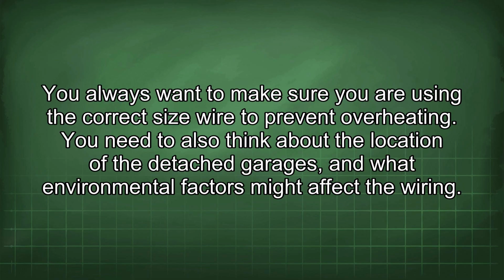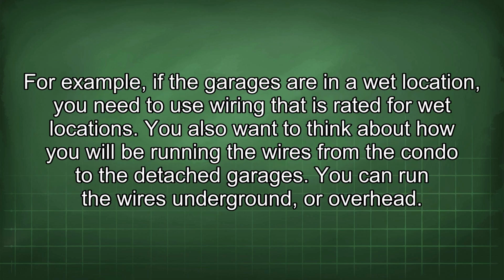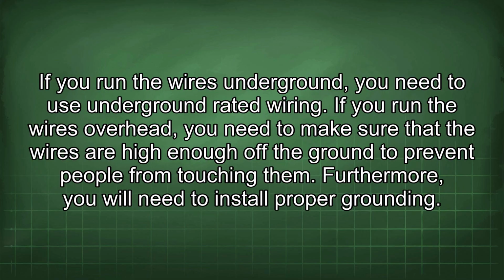You need to also think about the location of the detached garages and what environmental factors might affect the wiring. For example, if the garages are in a wet location, you need to use wiring that is rated for wet locations. You also want to think about how you will be running the wires from the condo to the detached garages. You can run the wires underground or overhead. If you run the wires underground, you need to use underground rated wiring. If you run the wires overhead, you need to make sure that the wires are high enough off the ground to prevent people from touching them.